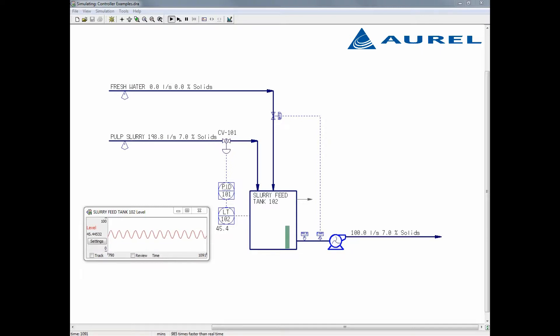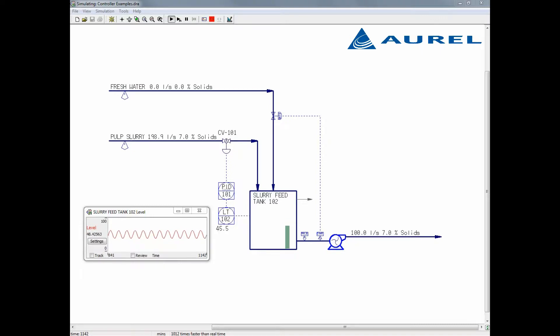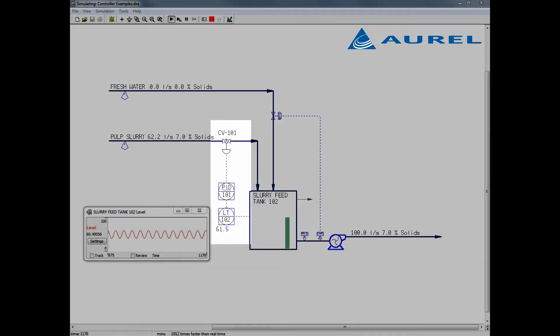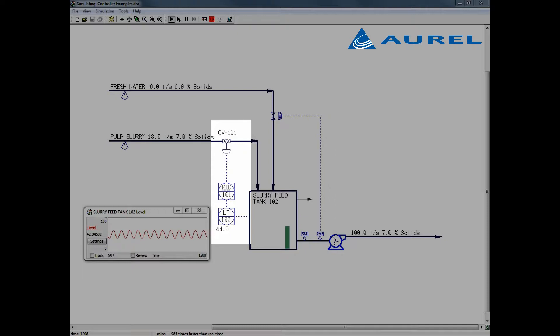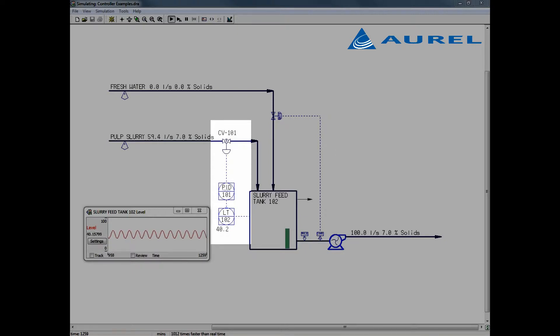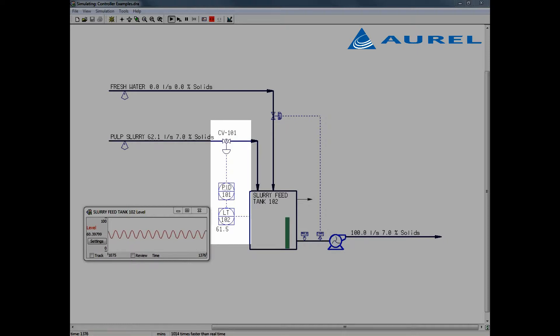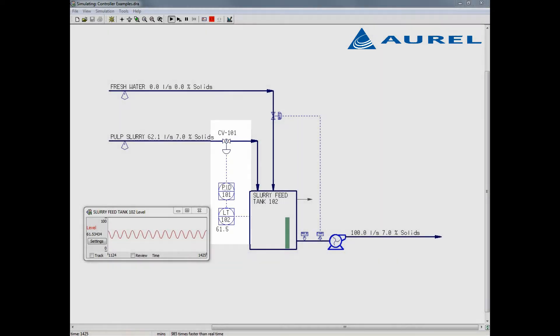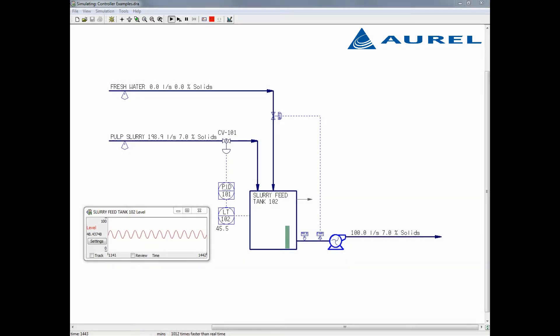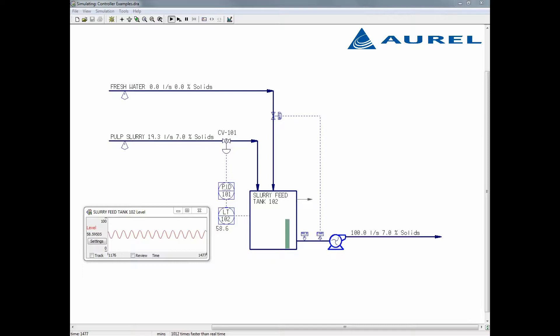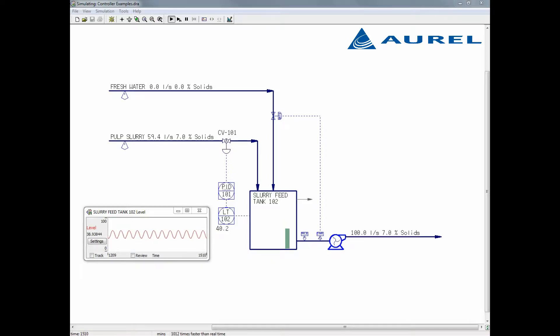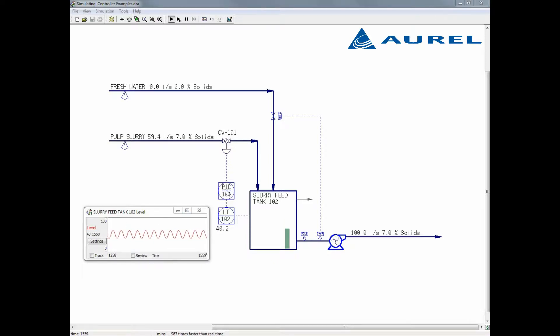First, I'll set up an integrating controller for the level and demonstrate how to tune it. I've drawn a controller as you might see on a P&ID. Here we see a level signal from the tank being sent to the PID controller. The PID controller changes the position of the valve which will in turn increase or decrease the flow of slurry into the tank as the situation requires. Right now, we can see the level in the tank is being poorly controlled because the PID has not been tuned well.